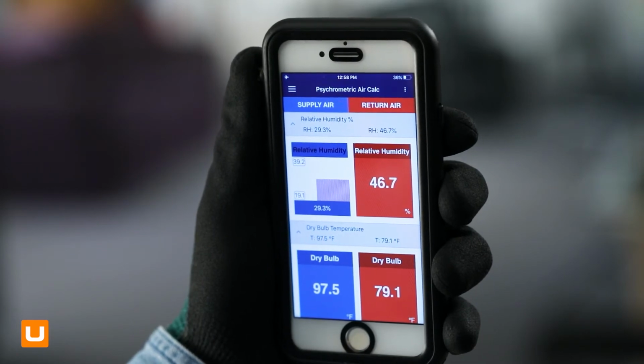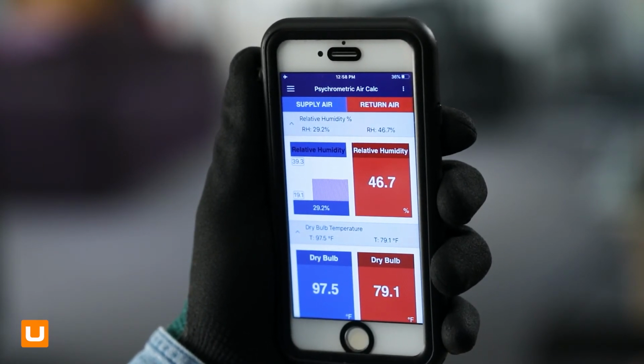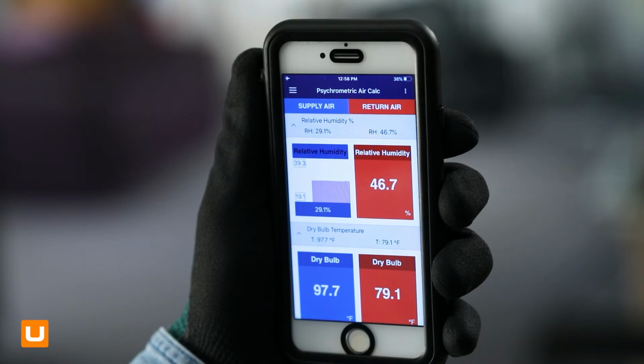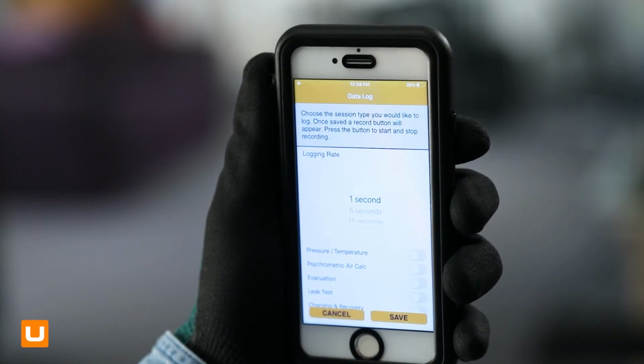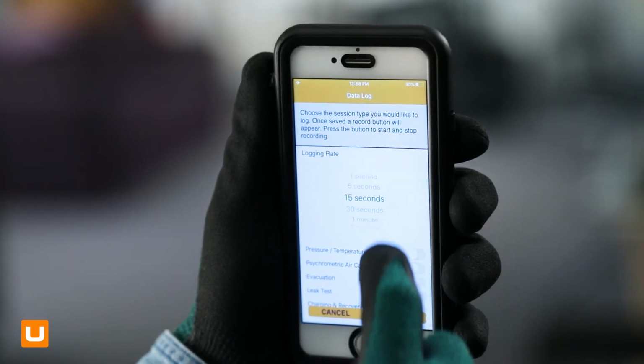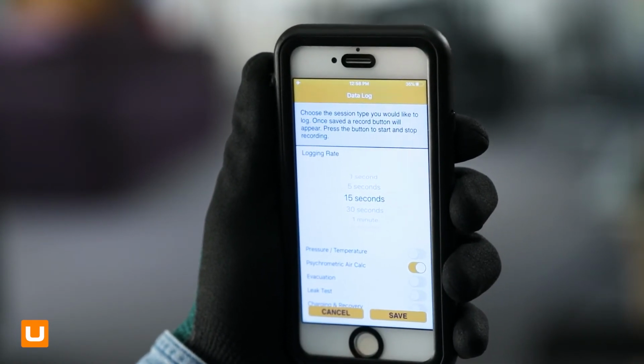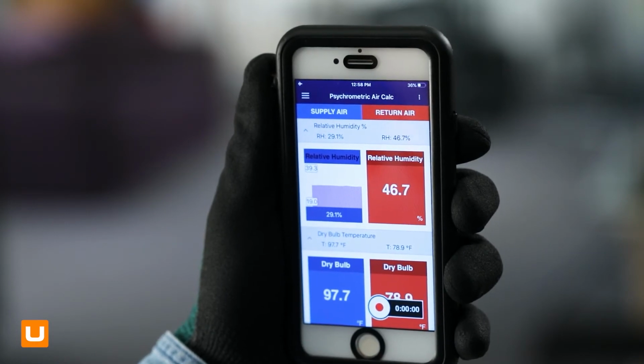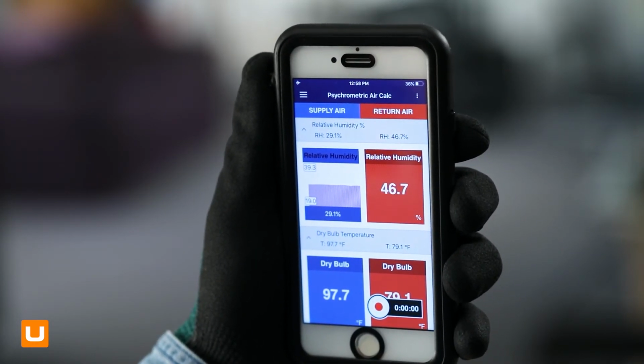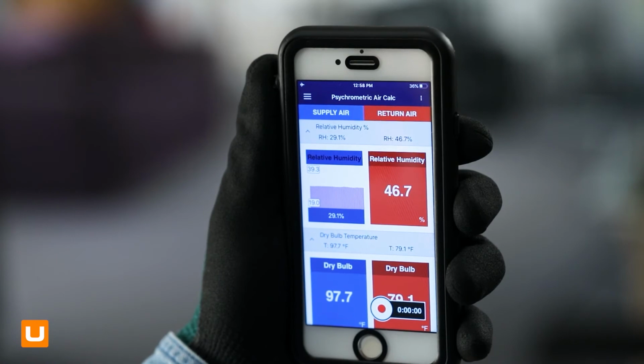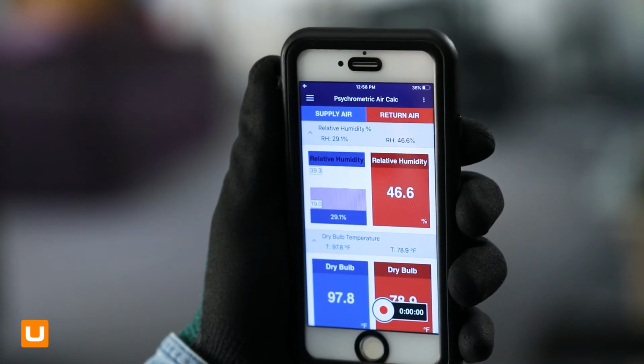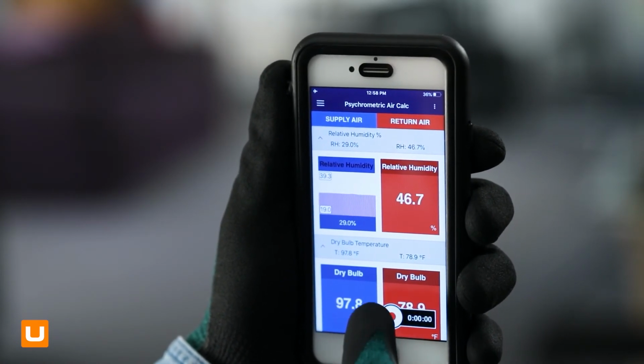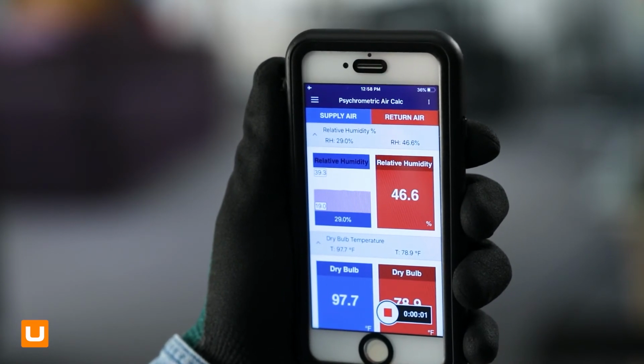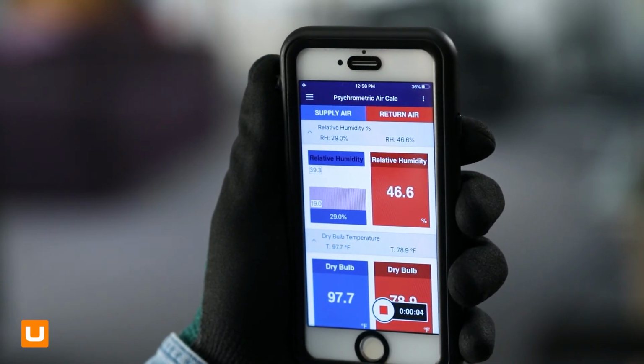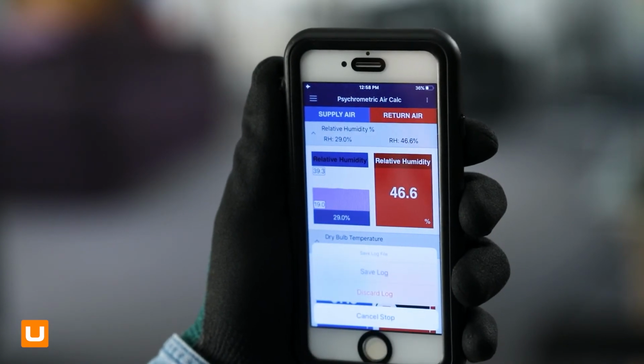To log the psychrometric data, tap on the 3-dot icon in the top right corner of the screen and select Create Data Log. Select the logging rate, toggle on the psychrometric air calculation session type, and tap Save. A recording icon will appear, and the data log can be started by tapping the icon. To end the data log, tap the Stop icon. You can then save and email the file for future reference.